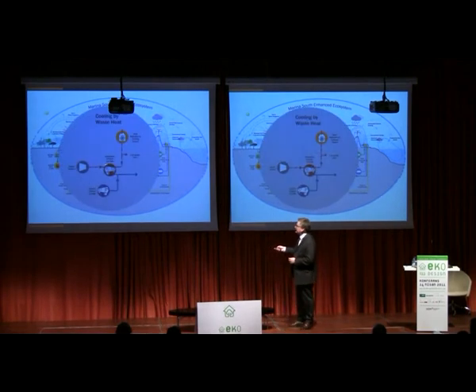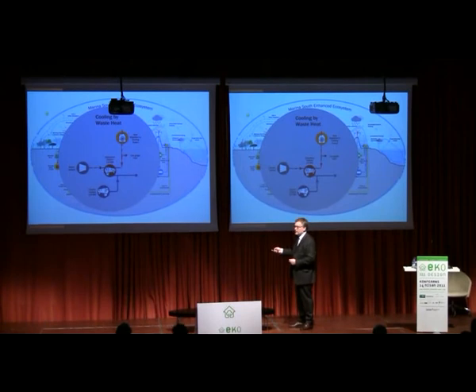Then the heat from that steam turbine goes into the waste heat, because it comes off as high pressure hot water, goes into an absorption chiller, which basically drives the first stage cooling in the gardens, with the electric chillers coming in with power off the turbines as a second stage. Any surplus heat is rejected.